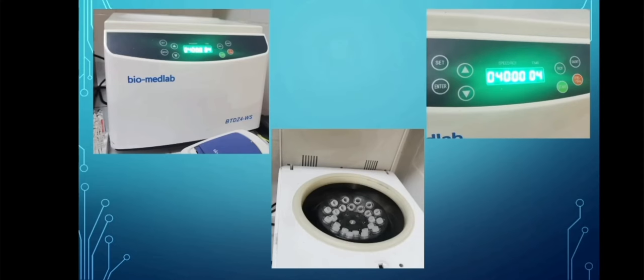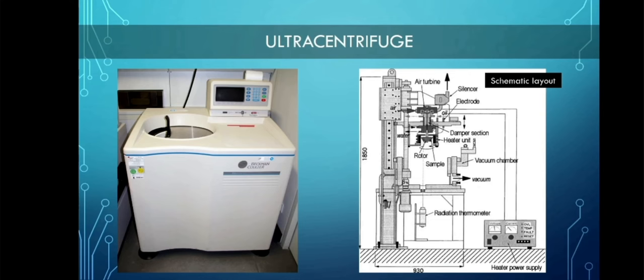This is a mechanical centrifuge. The highest RPM we have with this kind of centrifuge is up to 5,000 RPM or rotation per minute. The second type is the digital. It is slightly bigger than the mechanical centrifuge, can handle more specimens, and has a digital output.